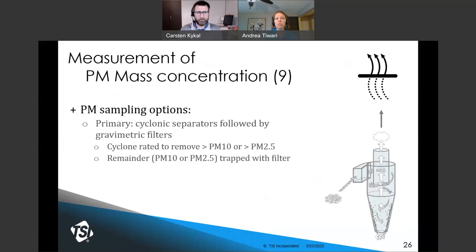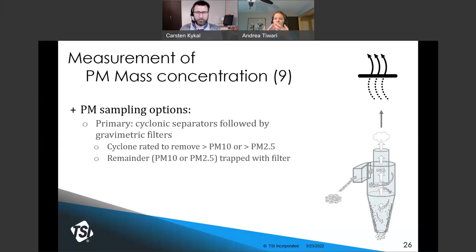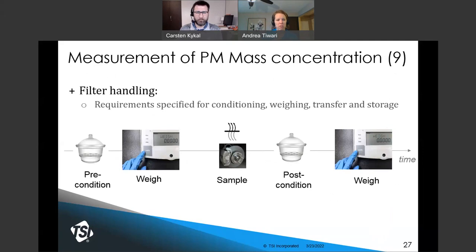Once particles are sampled isokinetically from the duct flow, they need to be collected so their mass can be measured later. The primary way to sample particulate matter is using a cyclonic separator followed by filtration. The purpose of the cyclone is to remove particles larger than the desired cut point — either 10 or 2.5 micrometers, depending on the cyclone design. The remaining particles are captured on a filter and that filter is then weighed. Brand new filters must be preconditioned at a specified temperature and humidity; the initial mass is measured, then sampling is done, and then that conditioning process is repeated before the final mass measurement.